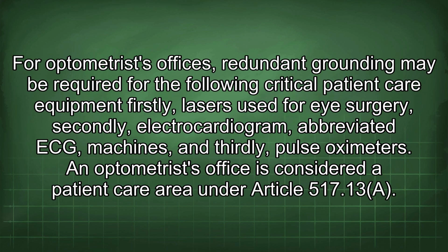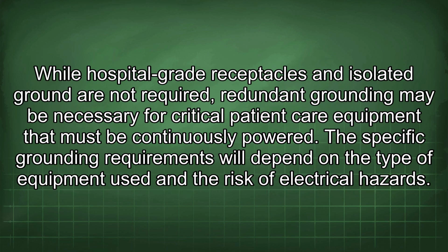For optometrist offices, redundant grounding may be required for the following critical patient care equipment: firstly, lasers used for eye surgery; secondly, electrocardiogram, abbreviated ECG machines; and thirdly, pulse oximeters. An optometrist office is considered a patient care area under Article 517.13a. While hospital-grade receptacles and isolated ground are not required, redundant grounding may be necessary for critical patient care equipment that must be continuously powered. The specific grounding requirements will depend on the type of equipment used and the risk of electrical hazards.